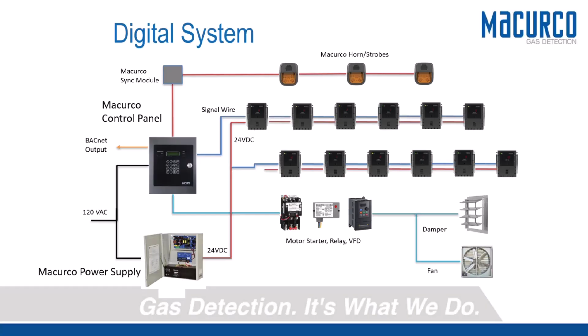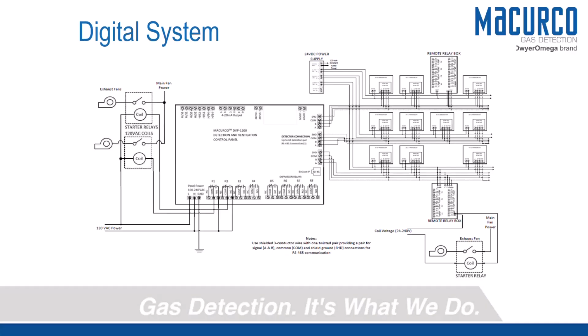At the end of the day, this is also pre-project—we can help you with risers and basically give you a footprint. We do a lot of this in the data center category as well as vehicle exhaust. In a data center, you have a huge square footage to cover and quite a few sensors, since you're dealing with combustible gas, so sensors need to be about 900 square feet apart—roughly 30-foot centers. We'll do a riser and give you an example based on your system.